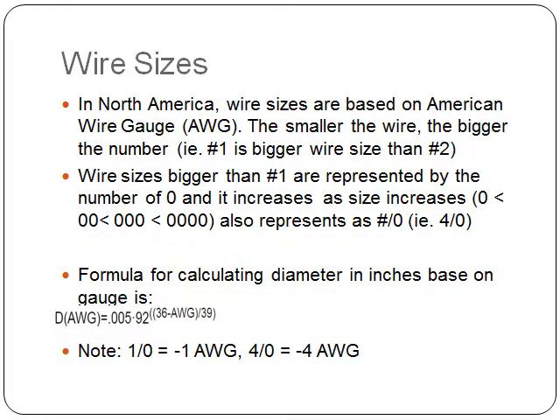Let's talk about wire sizes. In North America, wire sizes are based on American Wire Gauge, or AWG. The smaller the wire, the bigger the number — so number one is a bigger wire size than number two. Wire sizes bigger than number one are represented by the number of zeros, and the count increases as size increases: zero is smaller than double zero, which is smaller than triple zero, and so on. This is more commonly called 'aught,' so one zero is called one-aught, two zeros is called two-aught, and it can also be written in the form number-slash-zero.